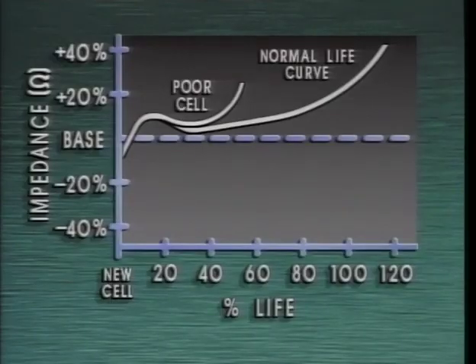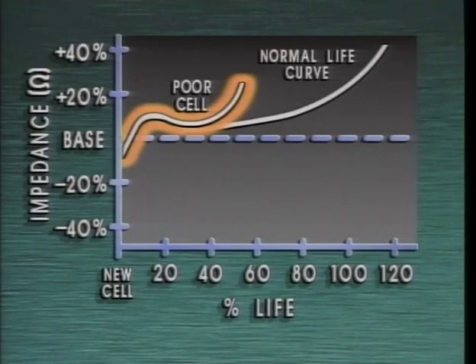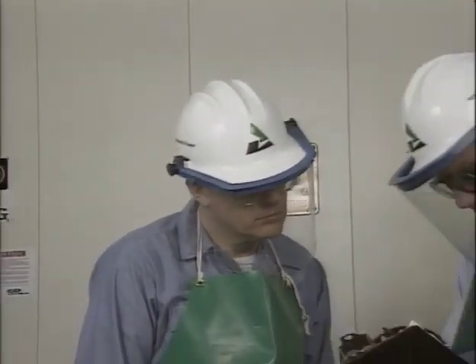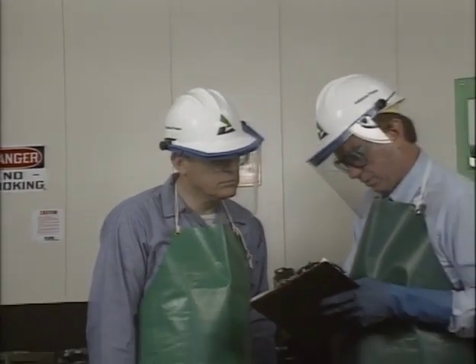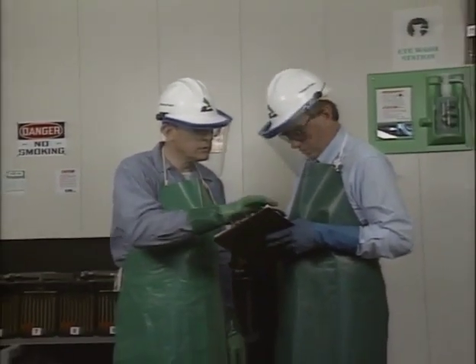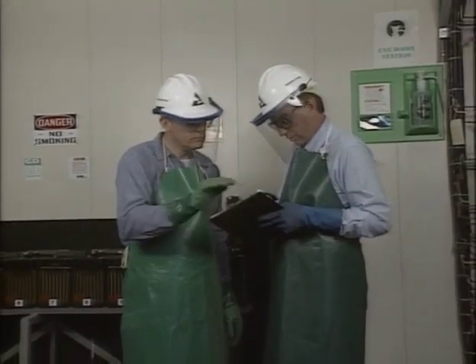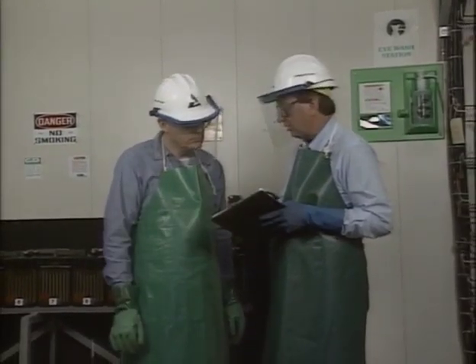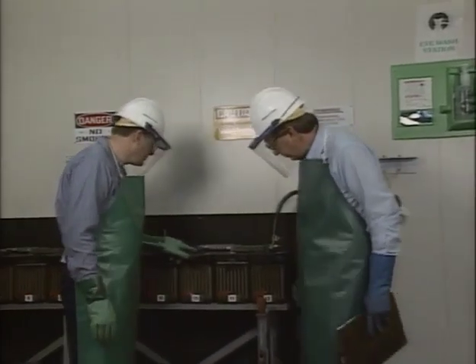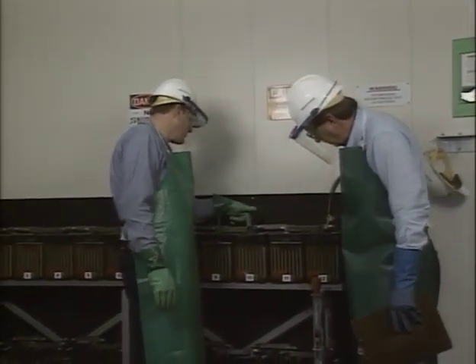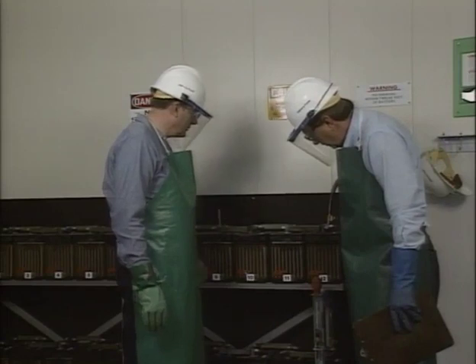Each cell impedance can also be charted with previous readings for the cell and compared to the normal cell impedance life curve. If there's a rapid increase in impedance, the cell or the entire battery may need to be replaced, depending on the age of the battery. The same historical comparisons can also be made for the impedances of intercell connections. Connection impedance is similar to connection resistance, although they cannot be directly compared. Connections showing significant increases in impedance may need to be thoroughly cleaned to reduce the impedance.